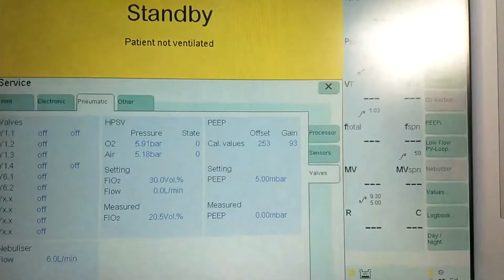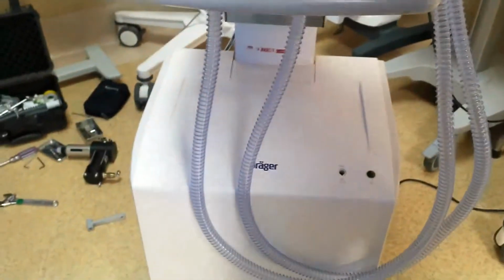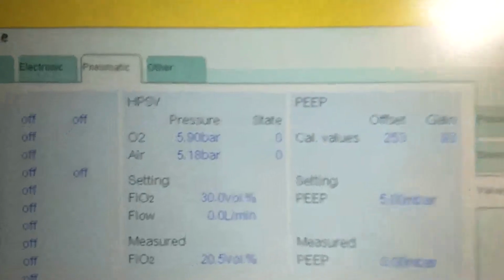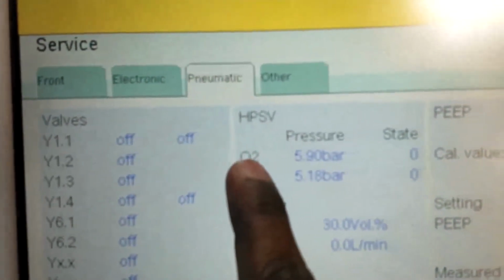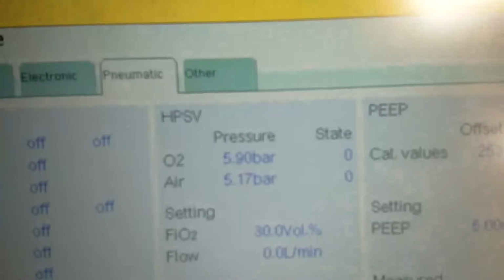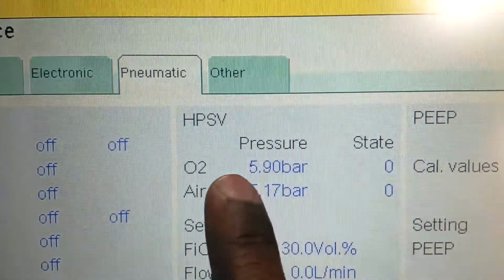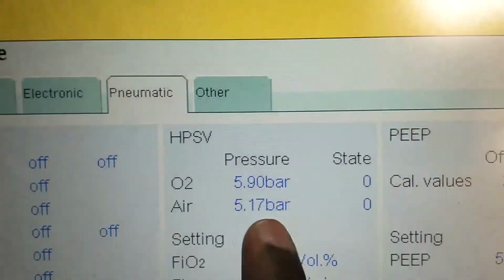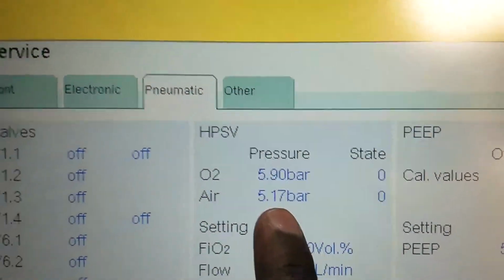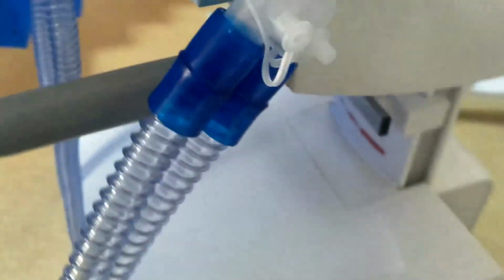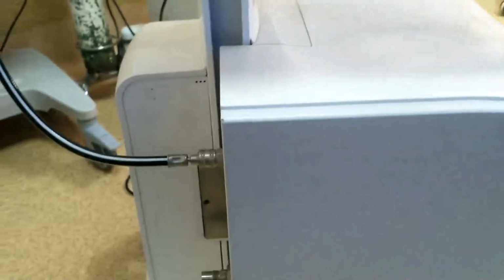Okay, once we are done solving the compressor problem, we will go and do a device check, the whole device check for the ventilator. Now you can see that the oxygen pressure is 5.9 bar, which is very good. And the air pressure is also 5.17 bar, and the air pressure is being provided by the compressor, as you can see.